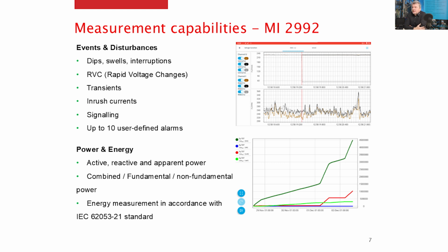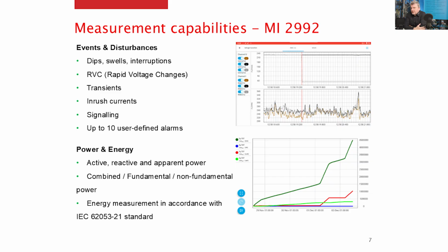Based on the event and disturbances, the instrument can simultaneously measure voltage dips, swells, interruptions, then RVC, rapid voltage changes, transients, inrush currents, signaling, and up to 10 custom user-defined alarms. Based on the power and energy, we are following the IEEE 1459 standard. So active, reactive, apparent energy and demand are measured accordingly, divided into the combined, fundamental, and then non-fundamental part.